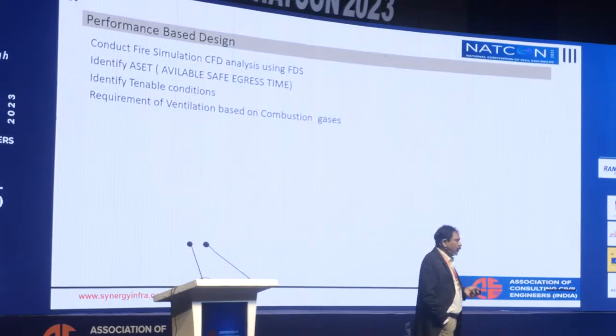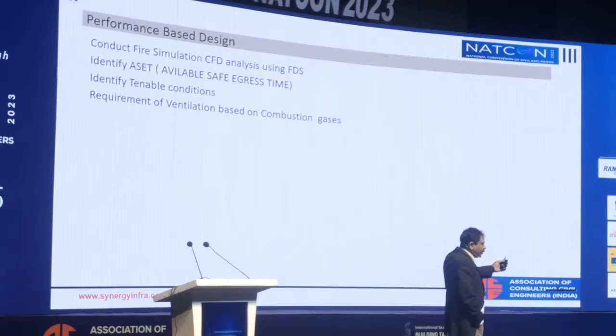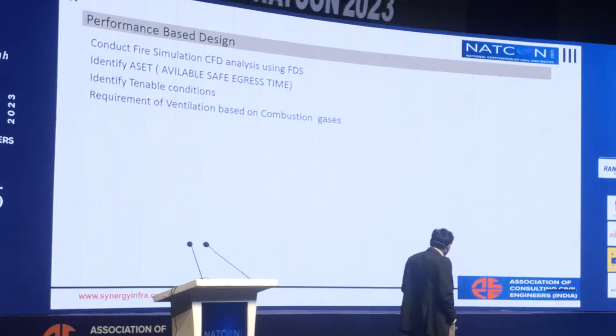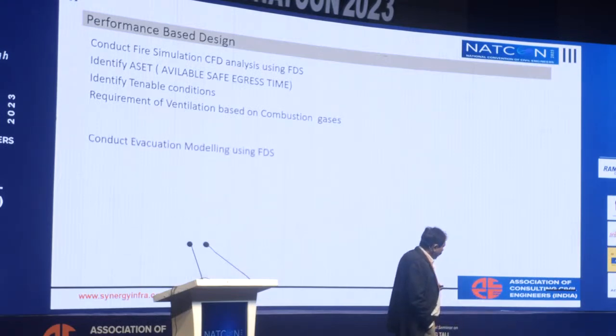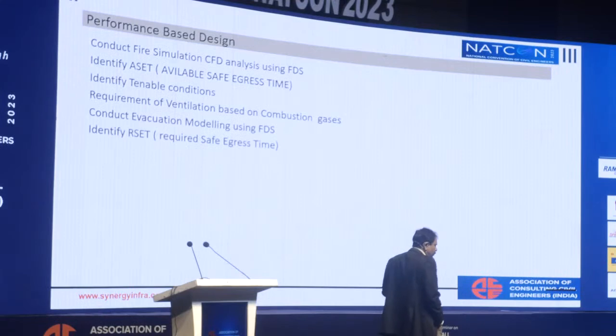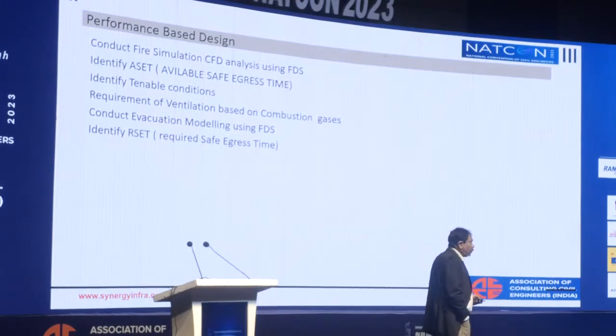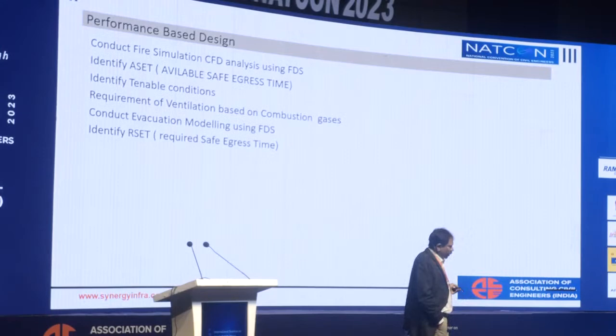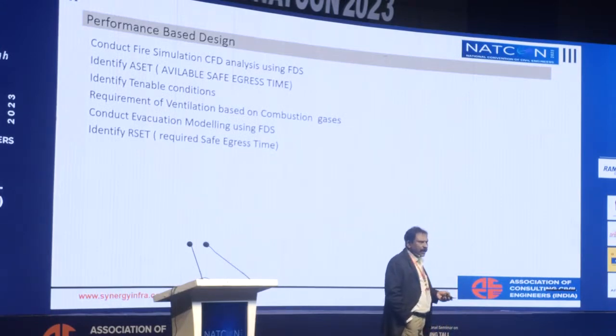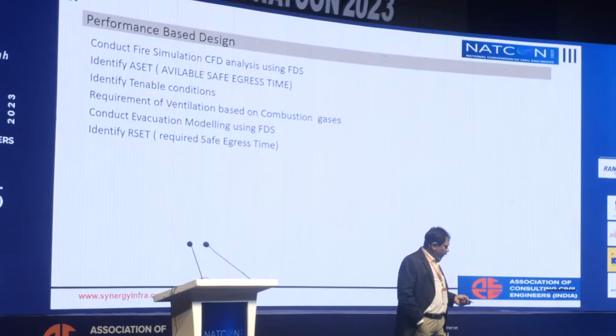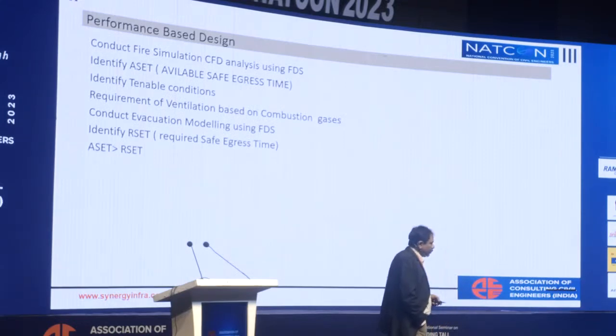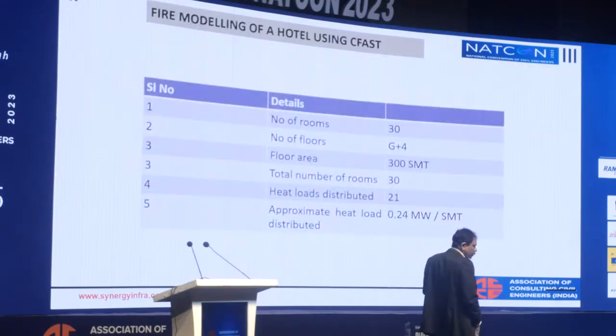For visibility, almost 47% of survivors said they couldn't see their own hands stretched out in the thick smoke, so that's the kind of smoke that can be generated. If these three tenable conditions are maintained, we can determine the available safe egress time and the ventilation requirements based on combustion gases, and also do evacuation modeling using FDS or other software like Pathfinder. I'll show you some models and we identify the required safe egress time; our available safe time should be more than the required time.